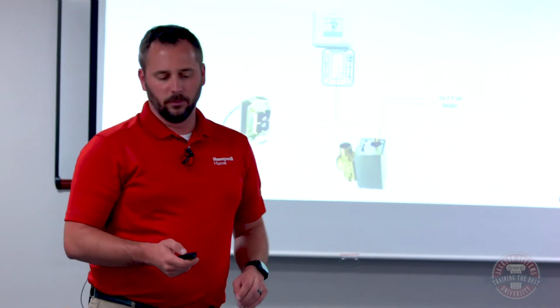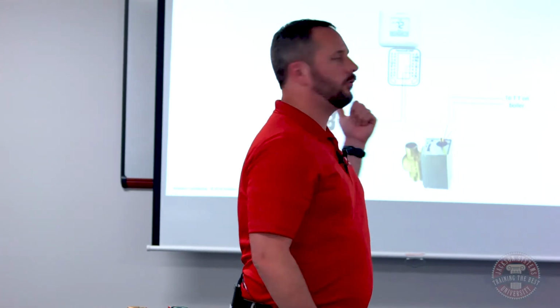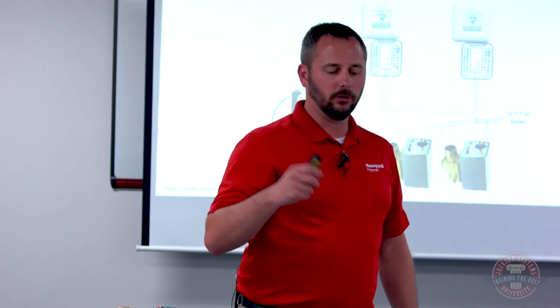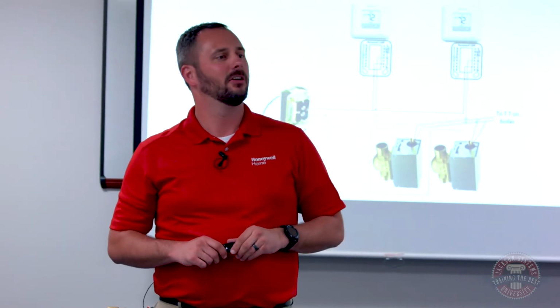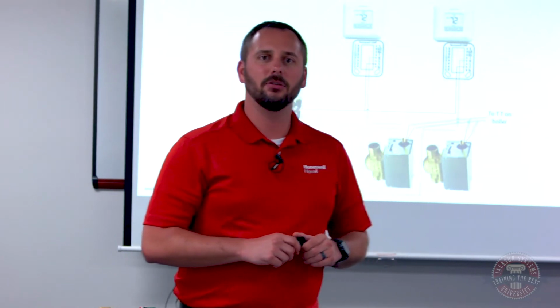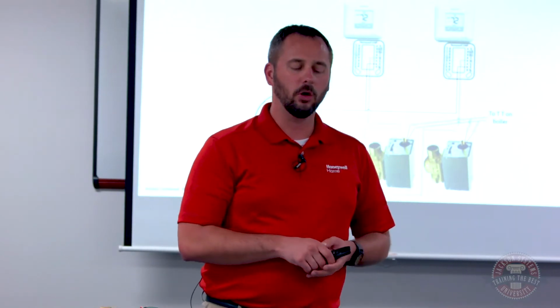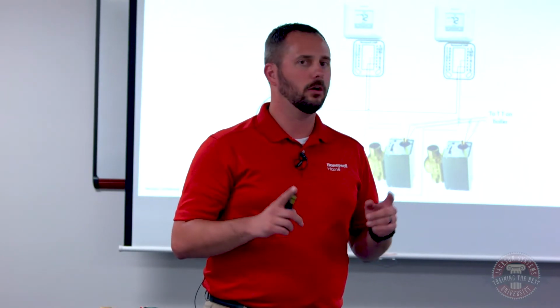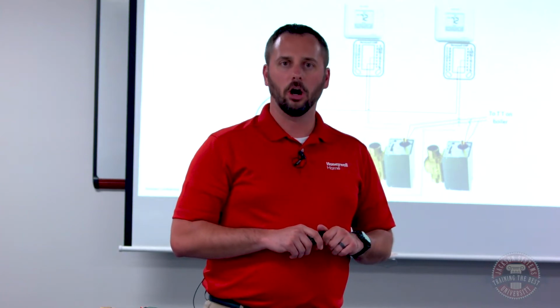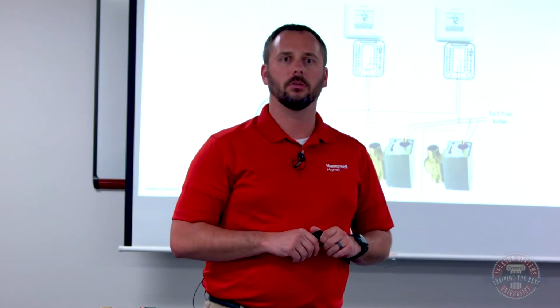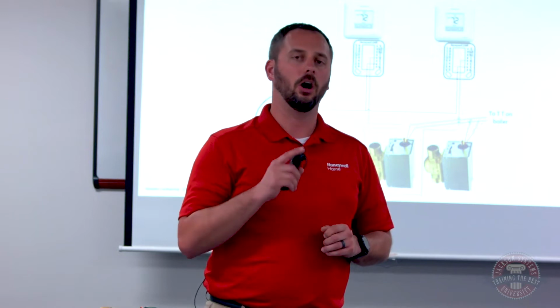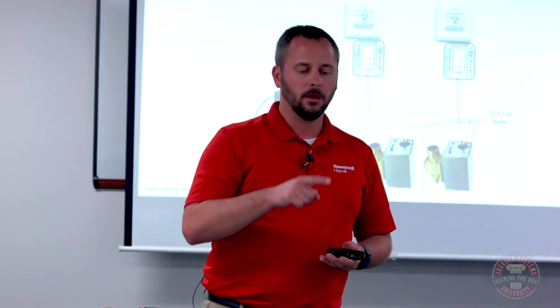The problem with this example I'm showing you is that there's really no one zone valve system that exists today. So what we do is we hook up 2 thermostats. So we've got 2 thermostats and 2 zone valves. We're taking R off the transformer and going up to R on both thermostats, so we're putting 24 volts on both thermostats. The W comes off of the corresponding thermostat to the corresponding zone valve.